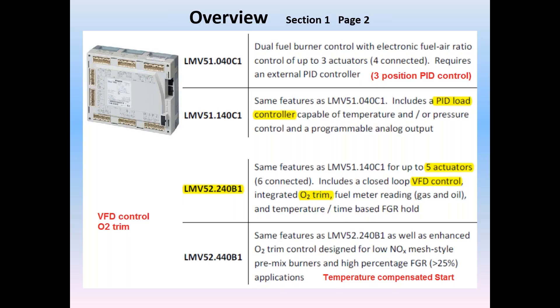Second is the LMV51140, with all the previous features, but includes an internal PID load control. Simply connect the temperature or pressure sensor and program the on and off points, as well as PID settings.